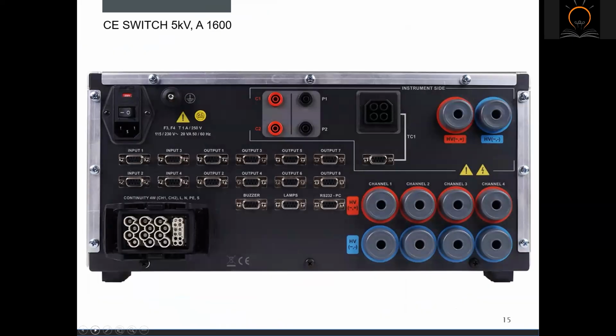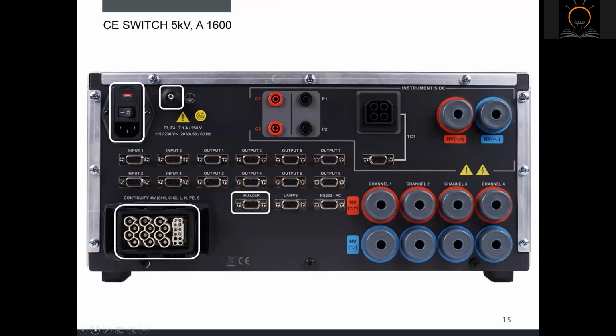On the back side of the adapter, we can find the following connectors and terminals. The first one is the screw-type protective earth connector for connection of a supplementary earthing cable. Then we have the mains supply connector with integrated on-off switch and fuses. Industrial plug intended for connection to various connection boxes. Currently we have 3 of them: A1626, A1627 or A1688. Then we have the buzzer connector and lamps connector for connection of LED signal towers.